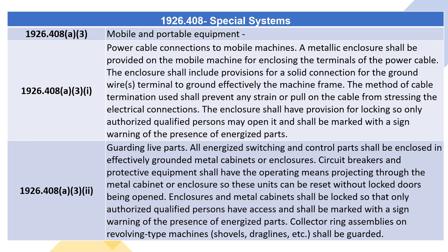1926.408(A)(3) — Mobile and Portable Equipment. 1926.408(A)(3)(i) — Power Cable Connections to Mobile Machines. A metallic enclosure shall be provided on the mobile machine for enclosing the terminals of the power cable. The enclosure shall include provisions for a solid connection for the ground wire's terminal to effectively ground the machine frame. The method of cable termination used shall prevent any strain or pull on the cable from stressing the electrical connections. The enclosure shall have provision for locking so only authorized qualified persons may open it and shall be marked with a sign warning of the presence of energized parts.